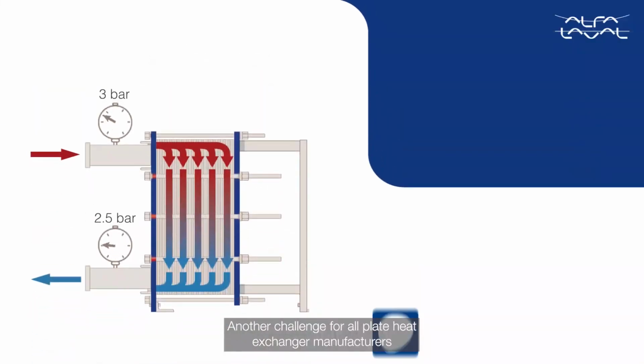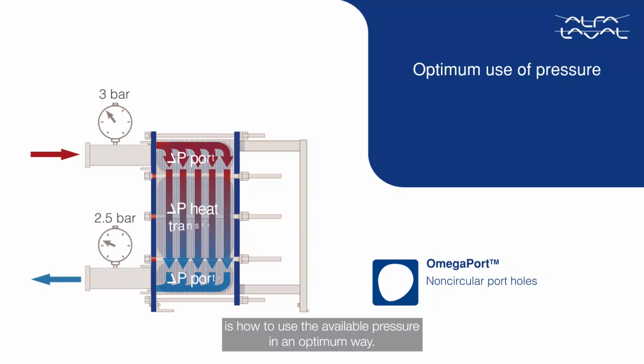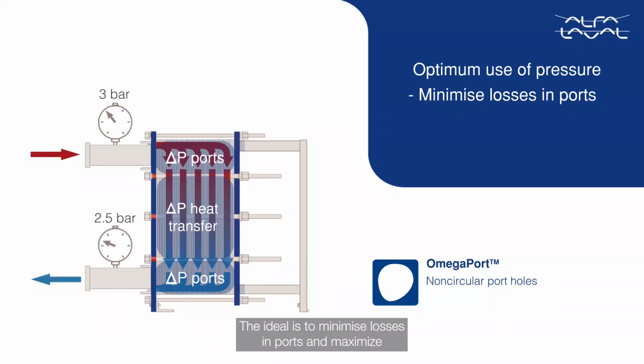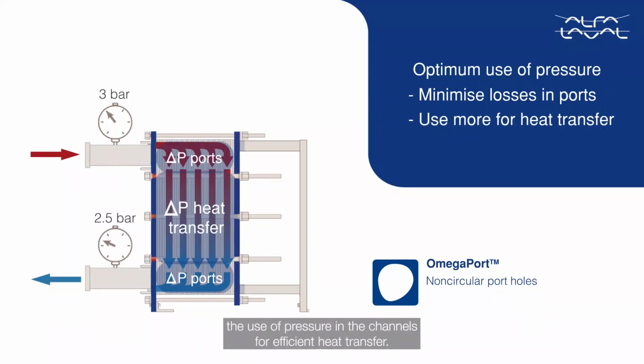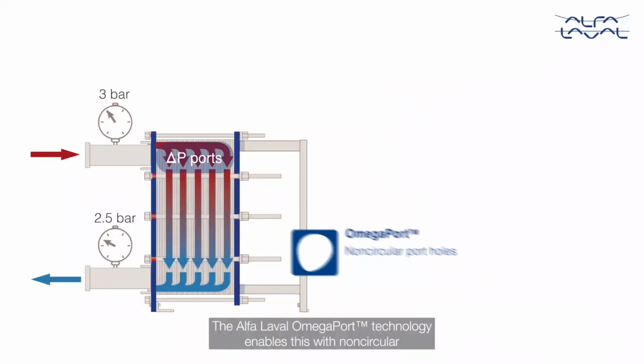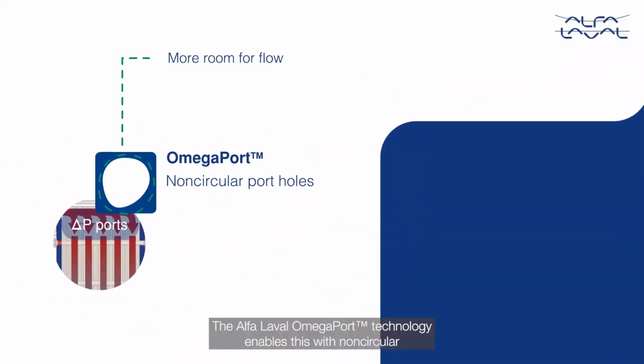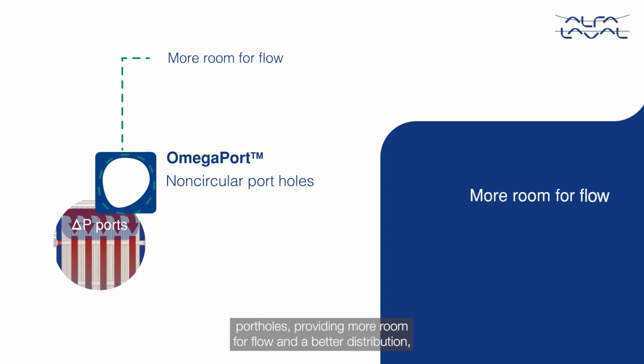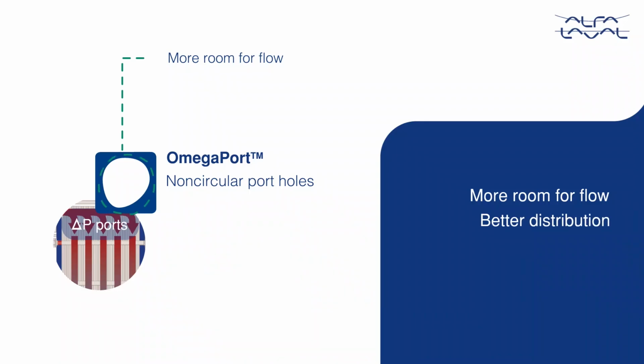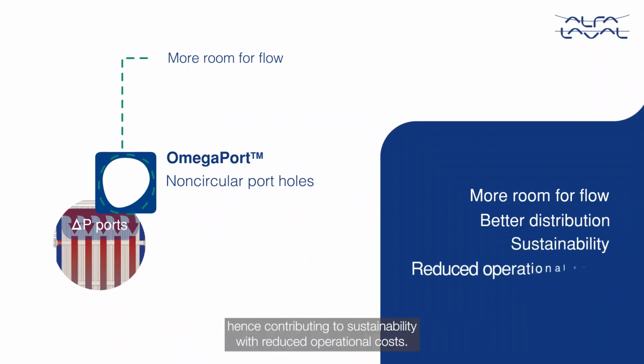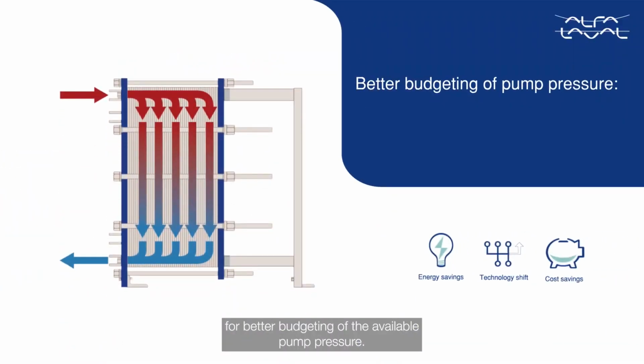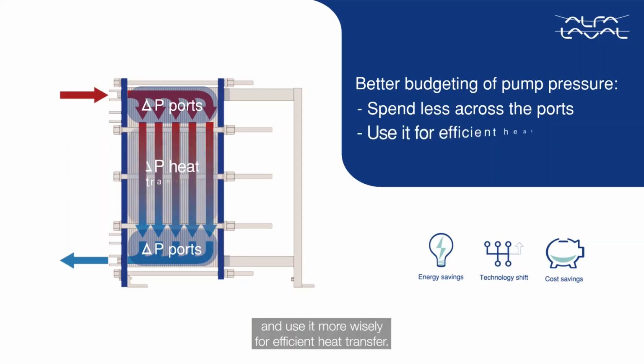Another challenge for all plate heat exchanger manufacturers is how to use the available pressure in an optimum way. The ideal is to minimize losses in ports and maximize the use of pressure in the channels for efficient heat transfer. The Alfa Laval OmegaPort technology enables this with non-circular portholes, providing more room for flow and a better distribution, hence contributing to sustainability with reduced operational costs. Pressure is money, and the OmegaPort helps for better budgeting of the available pump pressure. In other words, spend less across the ports and use it more wisely for efficient heat transfer.